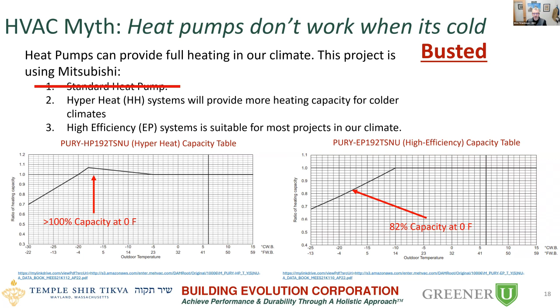So usually this rumor happens because of inappropriate selection of a heat pump for your climate. In our climate up here in Massachusetts, we would want a hyperheat or a high efficiency heat pump, depending on the building load or what part of the state you're in. For a hyperheat, in the table on the left, at about 0 degrees Fahrenheit outside, you're at over 100% capacity of that system. If you're at a high efficiency system, you're at 82% of its rated capacity at 0 degrees. So in those design day calculations for a lot of places, like Temple Shir Tikva, that is actually lower than the design calculation for the building. So either system is suitable for Wayland, Massachusetts, where this project is located.